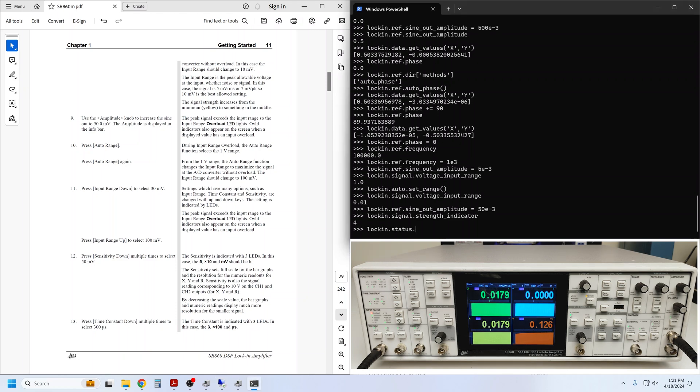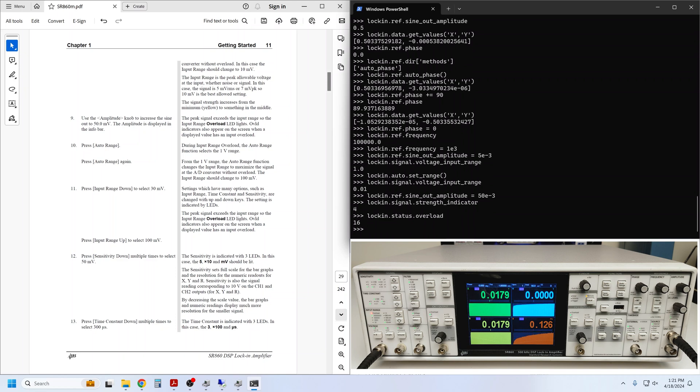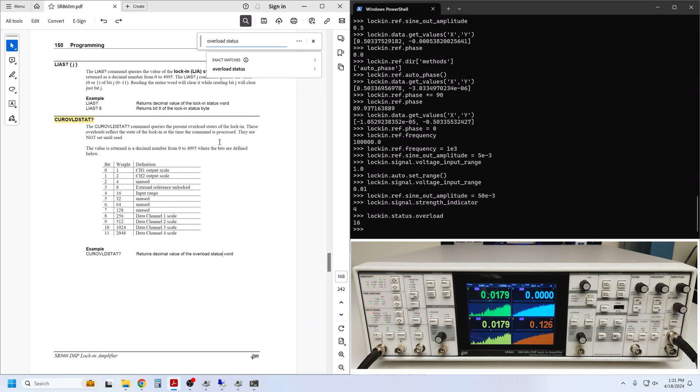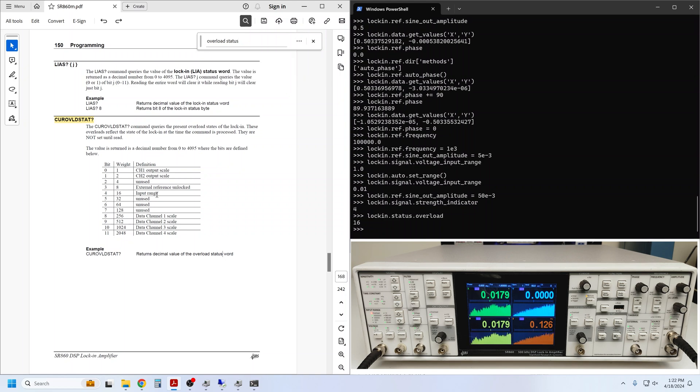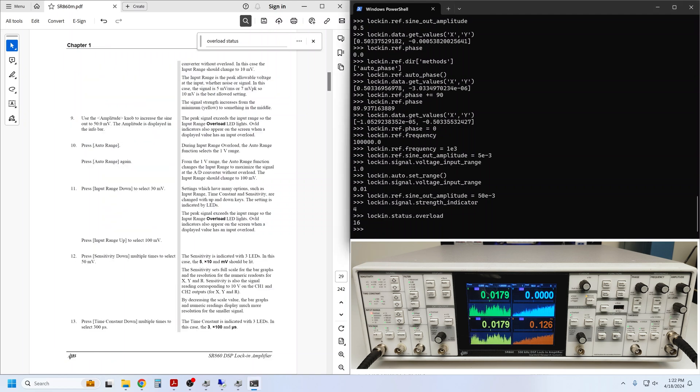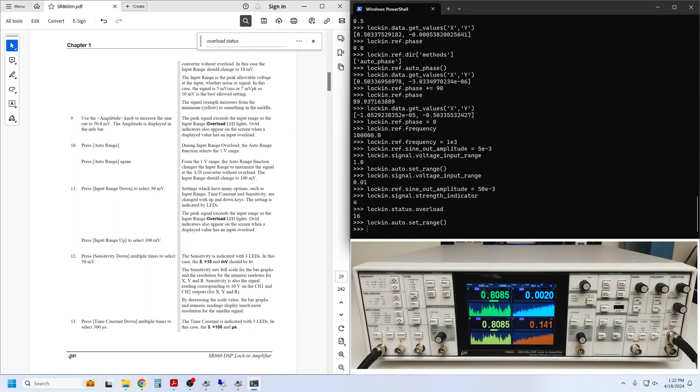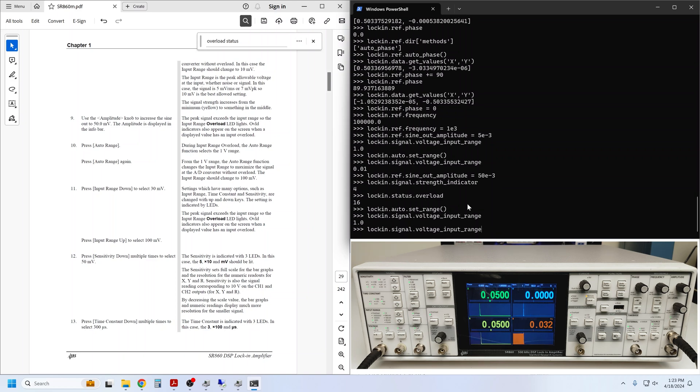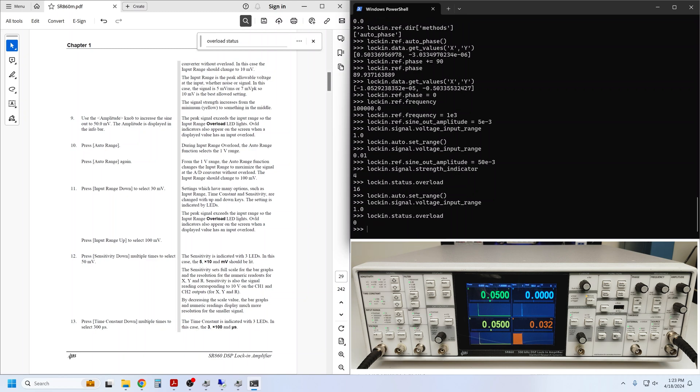Alternatively, we can ask the status what overloads are present right now. The overload_status returns a decimal number representing the binary weighted sum of all present overloads. Here we see that an overload status of 16 corresponds to an input range overload. We are instructed to execute an auto range again to pull the instrument out of overload. If executed during an overload, the auto range simply selects the maximum 1 volt input range.